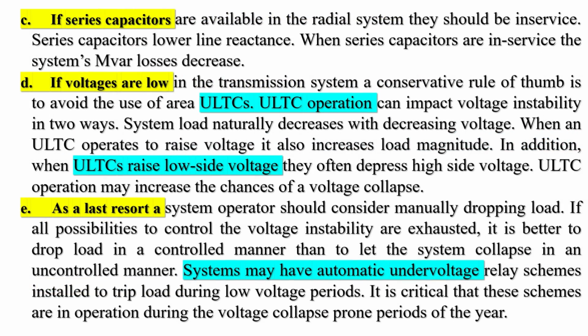C. If series capacitors are available in the radial system; they should be in service. Series capacitors lower line reactance. When series capacitors are in service, the system's MVAR losses decrease.